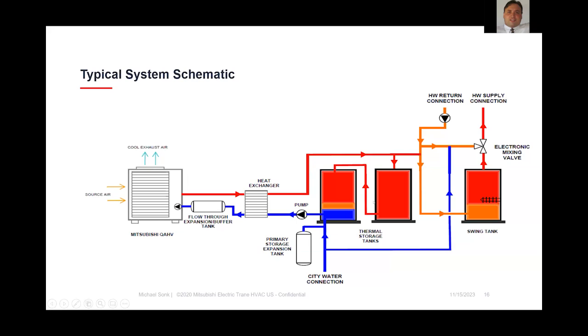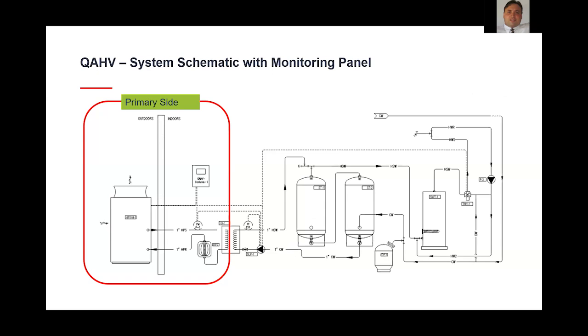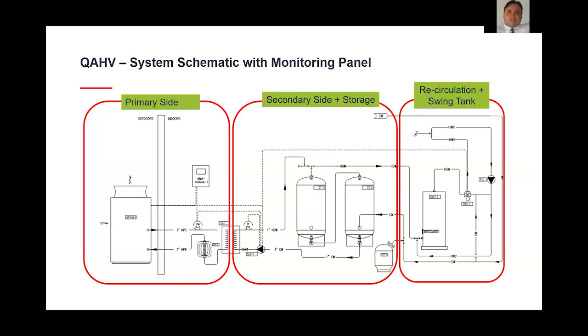This in a little bit more detail as we go through this. So you could really start breaking these systems up into three: primary side, which is your outdoor heat pump water heater with associated controls, all those closed loop components, that brazed plate heat exchanger indoors. And then what's called, again, as I mentioned before, the secondary side that has some additional controls, that variable speed pump, your primary storage tank farm, and then your recirculation and swing tank componentry.